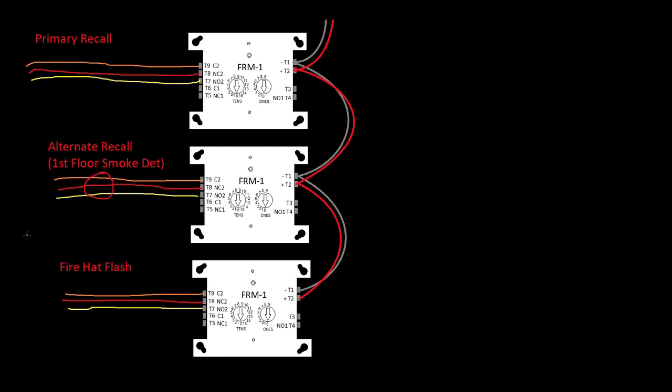As far as what these wires do once they're landed, it really doesn't matter to you. They typically tie the commons together, they won't use one of these, and so then they'll have like let's say it's 30 volts DC or whatever they're sending to you. They tie all the commons together and then they just get that signal back if they're normally open. You know, they'll get the 30 volts back on this one terminal. So usually you'll see like all your commons will be wire nutted in their panel and then they're just using that return, the switch leg essentially, from each side of it. But I'm digressing a little bit here.